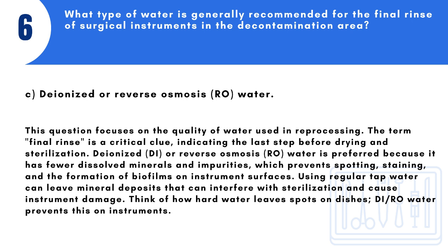Using regular tap water can leave mineral deposits that can interfere with sterilization and cause instrument damage. Think of how hard water leaves spots on dishes. DI/RO water prevents this on instruments.